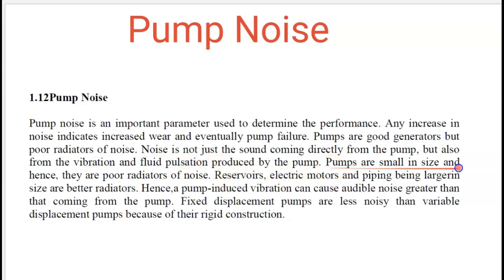Pumps are small in size and they are poor radiators of noise, but they can create noise. Reservoirs, electric motors, and piping, being large in size, are better radiators. Hence, pump-induced vibration can cause an audible noise greater than that coming from the pump.